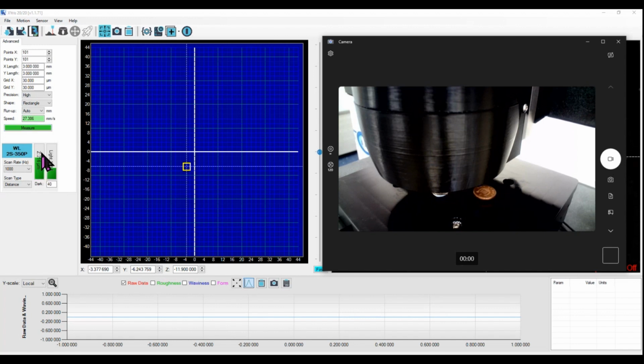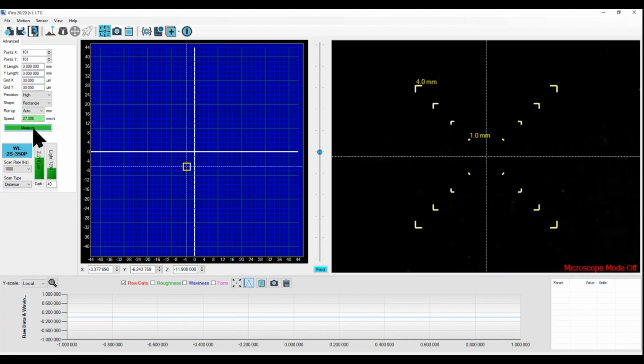Before I do that, I'll just point to this column here. This is an indication of the sensor output within its range. The current sensor that we're using, it's not visible in the camera view, but it has a full-scale range of 350 microns. And you can see it's roughly in the middle of that range. To the right of that is just an indication of the amount of light that's being returned to the sensor, which can be used for various measurement principles if you wish to use that. But we're currently measuring a height property, and all I'm going to do is click measure.